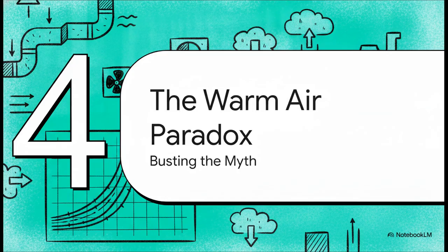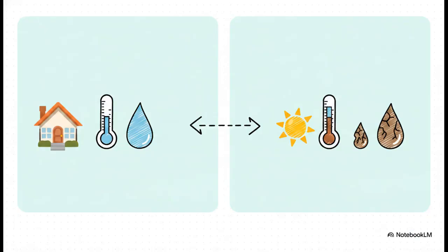Which brings us right to the climax of our explainer, Part 4, the warm air paradox. It is time to bust a major temperature myth. All right, let's circle back to that crazy opening question I asked you at the very beginning. We're going to pit 75-degree indoor return air against slightly warmer 77-degree outdoor air. But here are the missing details I withheld earlier. That 75-degree inside air is sitting at 50% relative humidity. The warmer 77-degree outside air is much drier, sitting at only 30% relative humidity.